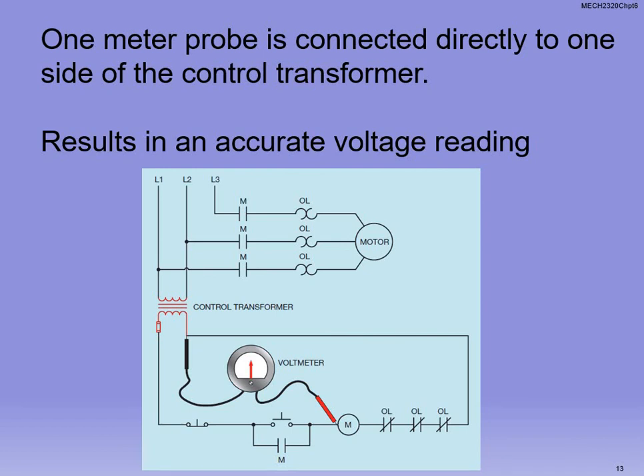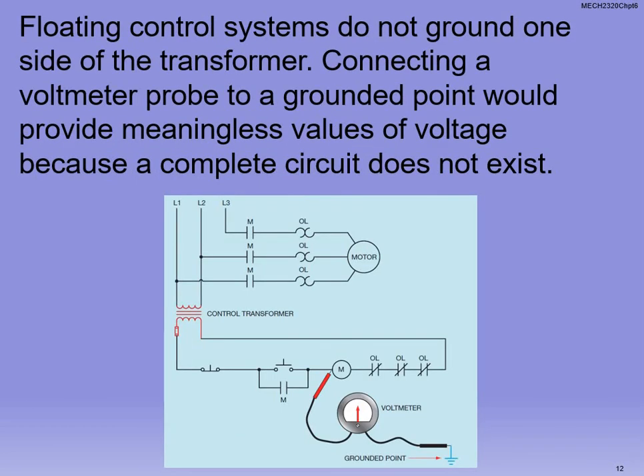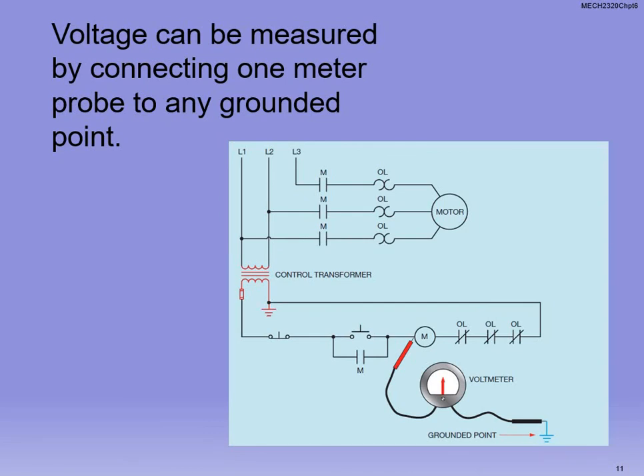We do not, I'm going to back up a slide here, we do not use this method to read the voltage across the motor or anything. Okay, it's a float system. It gives us ghost voltages. So this method only works, I'm going to step back a slide here again, if the control transformer is grounded. Notice on the schematic there's a ground symbol there by the control transformer. This method works. So if the control transformer is grounded as such, we can use the voltmeter here to take a reading because the ground point and ground there mean the same thing.